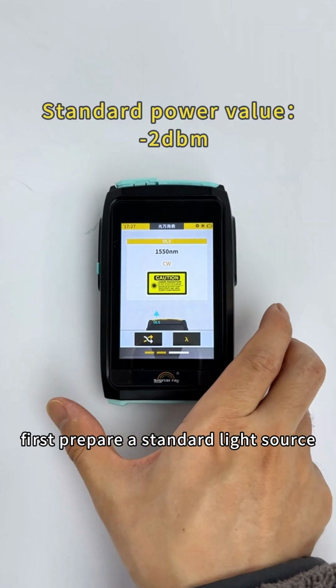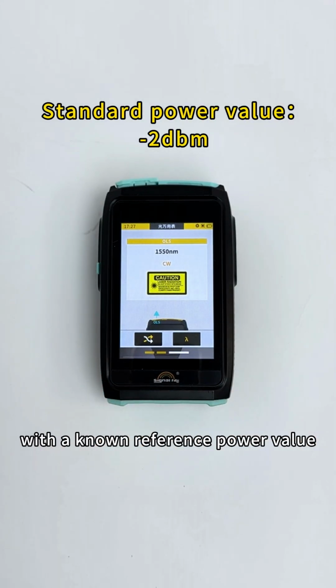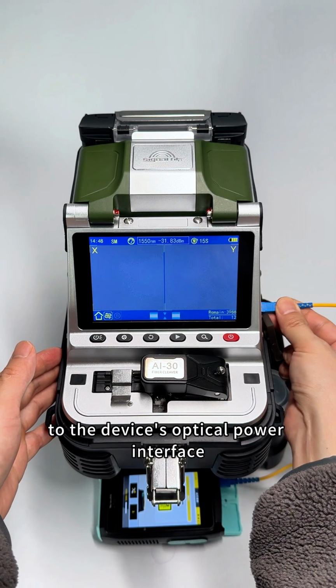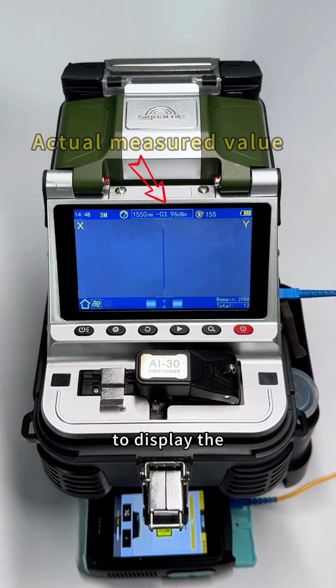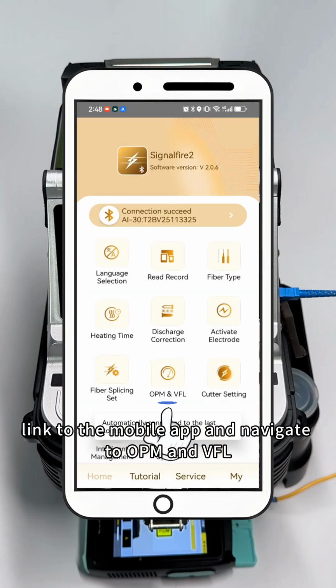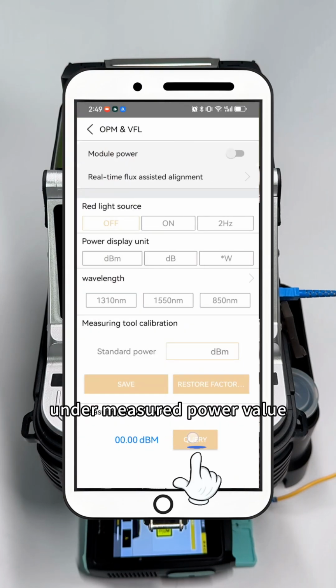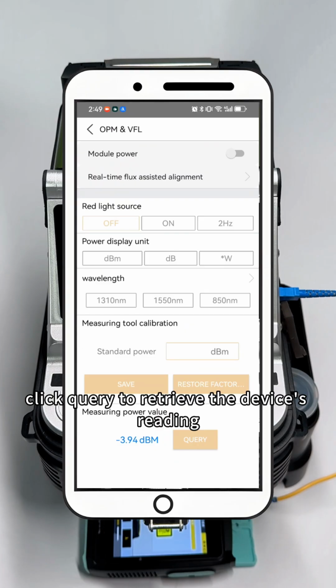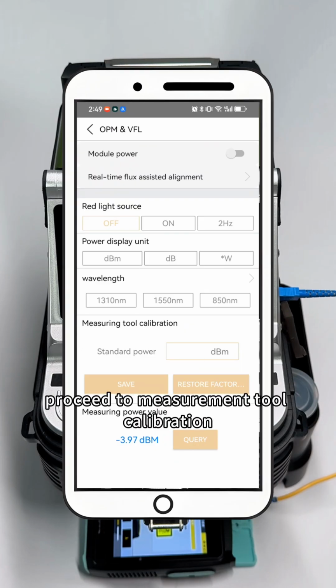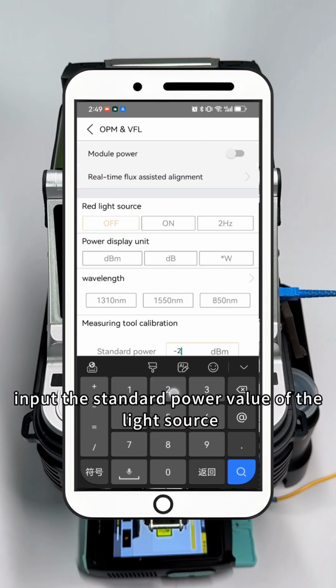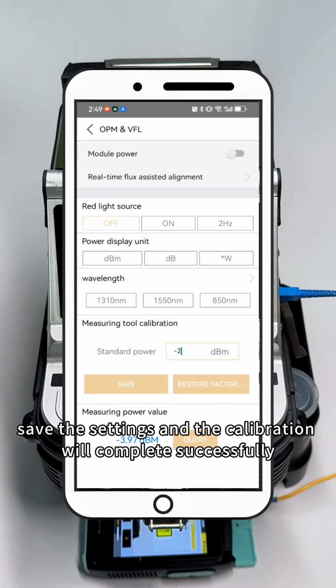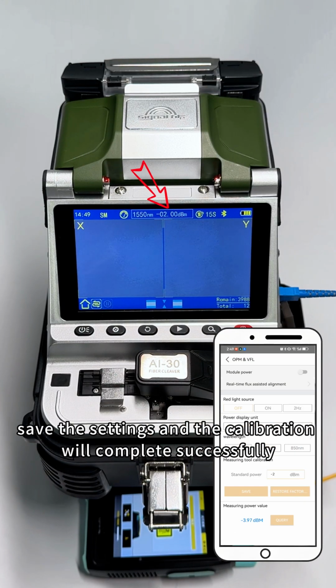First, prepare a standard light source with a known reference power value. Connect the standard signal to the device's optical power interface to display the actual measured value. Then, link to the mobile app and navigate to OPM and VFL under Measured Power Value. Click Query to retrieve the device's reading. Proceed to Measurement Tool Calibration, input the standard power value of the light source, save the settings, and the calibration will complete successfully.